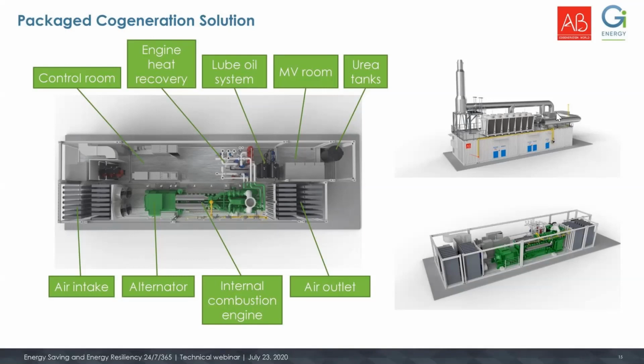Staying with the left side of your screen to cover the balance of plant components: we have a secondary container that includes the heat recovery system in the center. As mentioned, heat can be recovered through the cogen unit, and that heat comes from two sources. Source number 1 is the engine cooling system - there's a hot water loop keeping the engine at nominal operating temperature, and through a set of pumps, valves, and heat exchangers, we can make that heat available as hot water or even cold water to a customer.